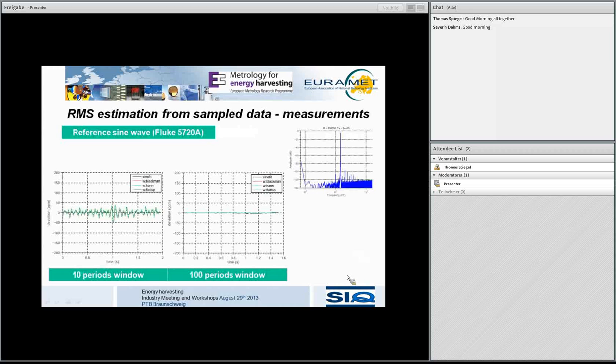So what we did further was check a very well-known signal — the AC signal from the Fluke 5720 reference calibrator. We used this windowing approach and another well-known sine fit approach, with a 10-period window moved across the signal to see the response. We saw something like 30-40 ppm deviation in the signal, which is a known characteristic of this calibrator, since it's not so stable over short time periods.